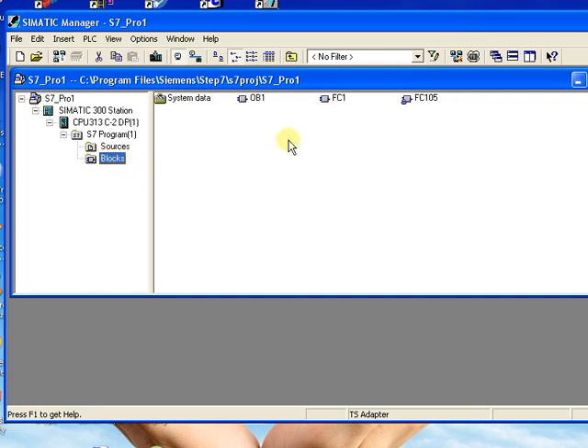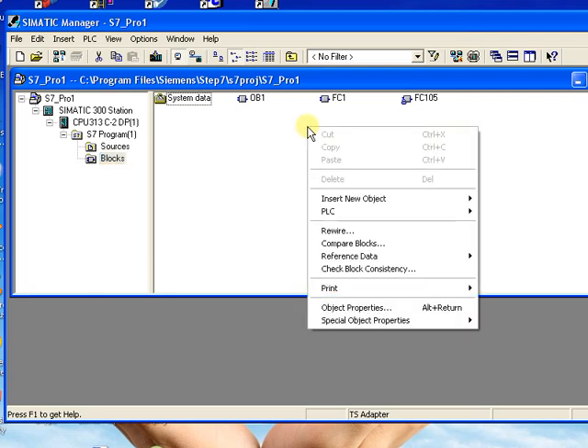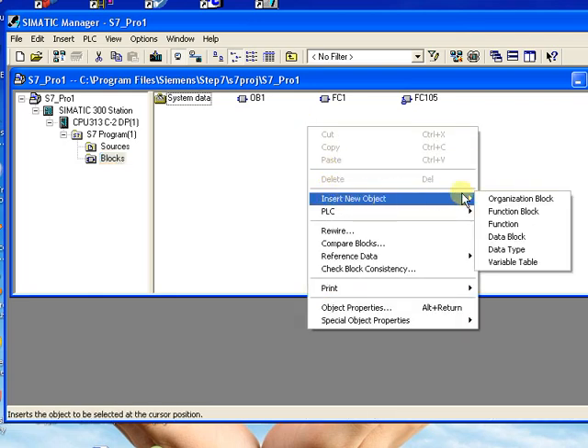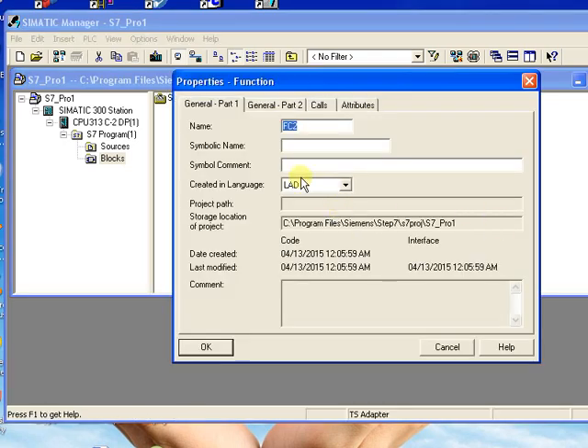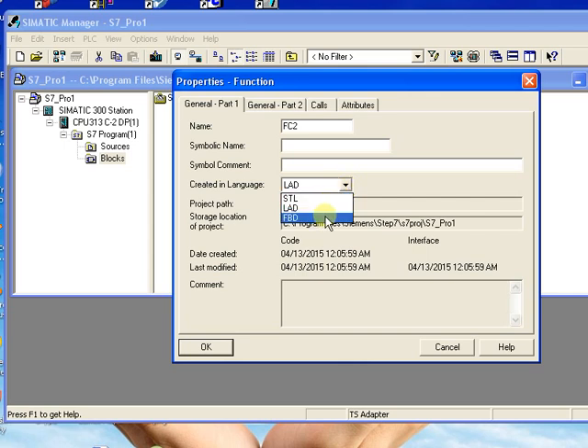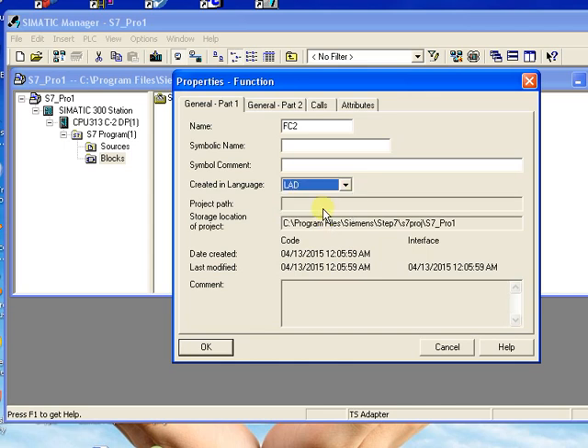Now come to the programming. Click the plus button, click Blocks, and you will see all the programming blocks listed here: first the OB block, then the FC block. Click Insert New Object, click Function — a new block is added. Click Ladder for ladder diagram, STL for statement list, or FBD for function block diagram. I will click Ladder and then OK.